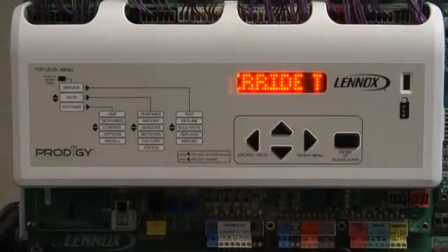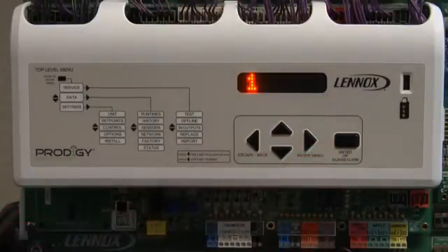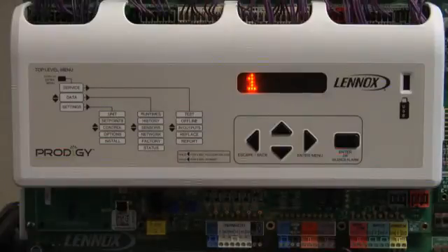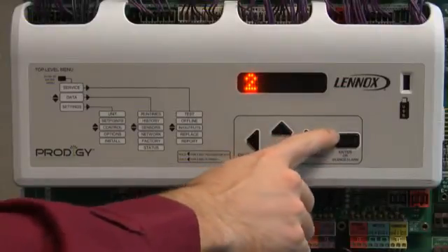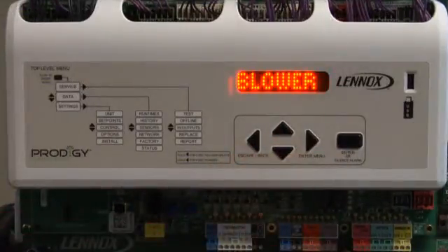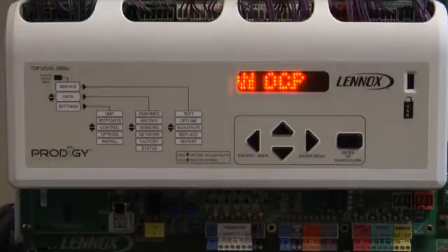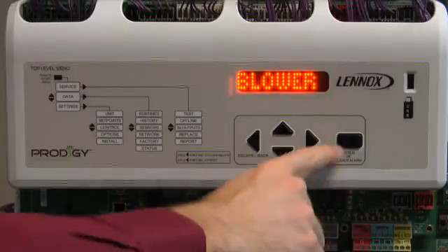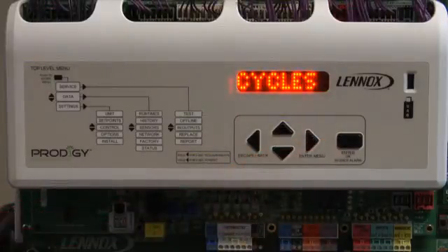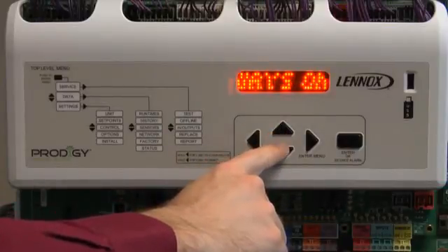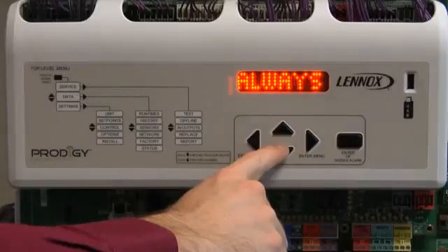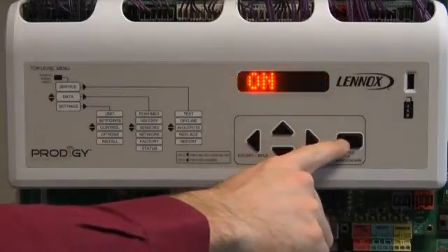Override timer will be displayed. Press enter. 1 will be displayed. Use the up or down arrow to adjust the override time, then press enter. Blower on occupied will be displayed. Press enter. Use the up or down arrow to adjust the set point. For this demonstration, we will use Always On. Press enter.